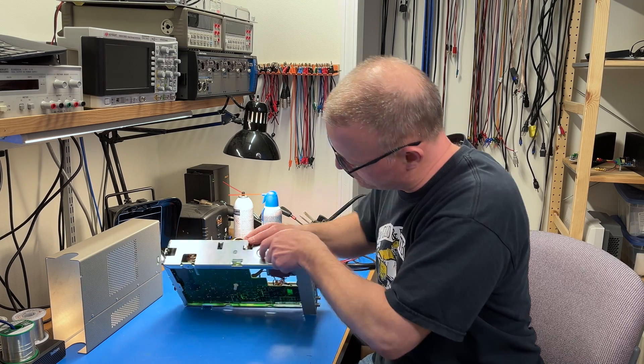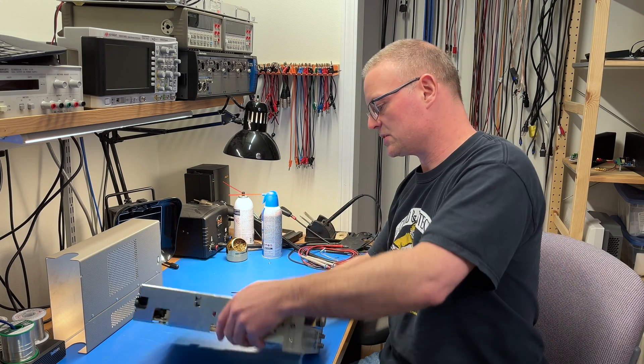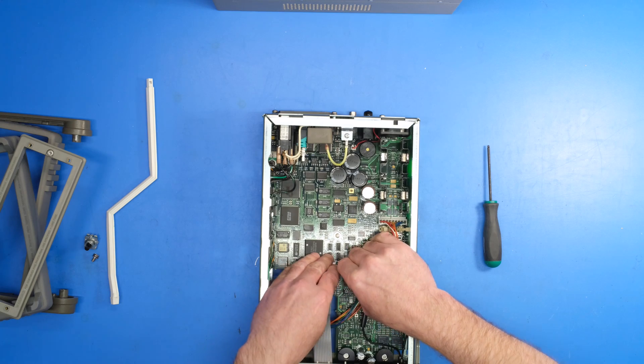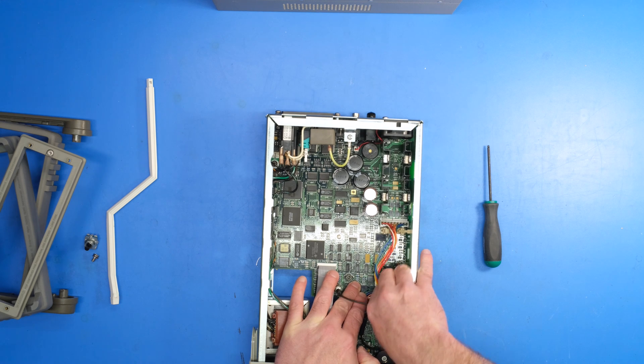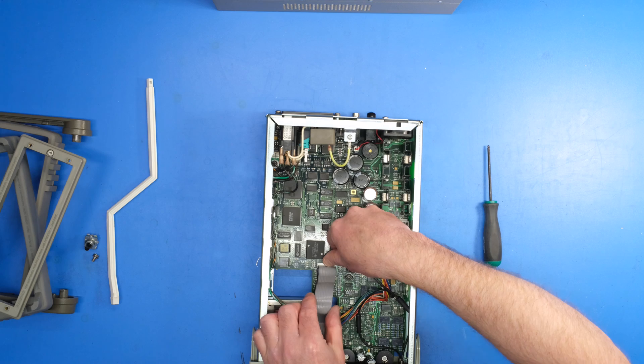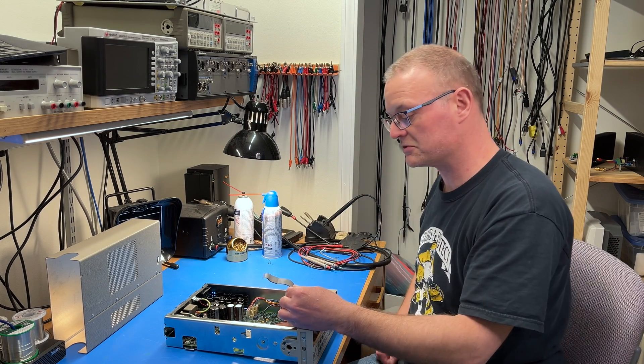Of course it's stuck somewhere. There we go. And then these cables that connect to the front panel need to be disconnected. The coax cables are pretty easy — they should just pop straight out. And then this ribbon cable here, I'm supposed to be able to push down the connector and it should come straight out. There we go — it's just a ZIF socket type deal.